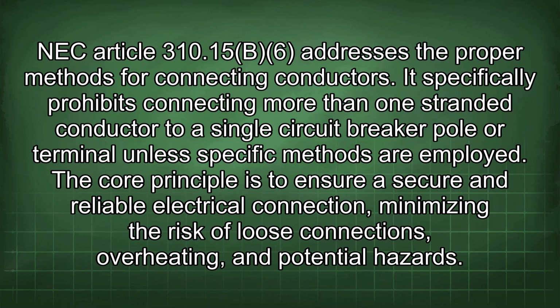NEC Article 310.15(B)(6) addresses the proper methods for connecting conductors. It specifically prohibits connecting more than one stranded conductor to a single circuit breaker pole or terminal unless specific methods are employed.